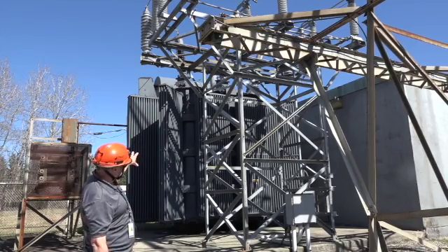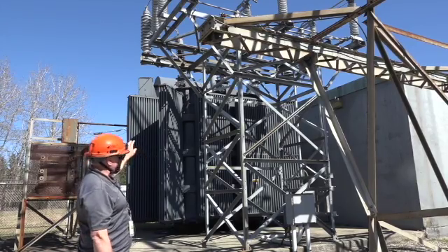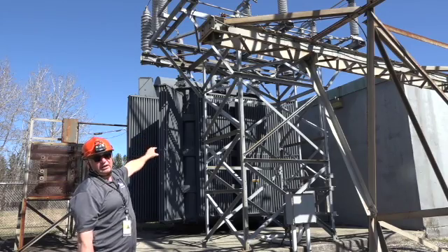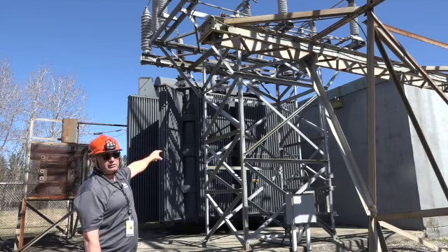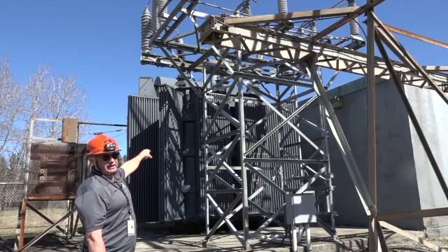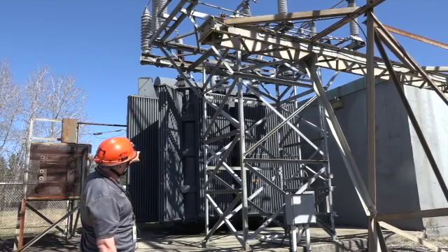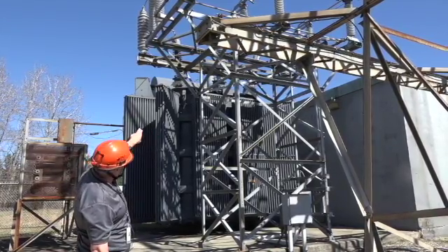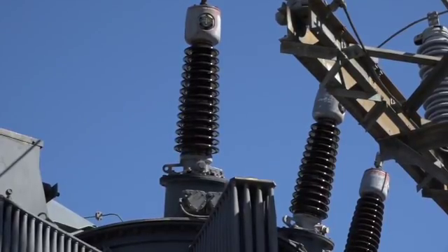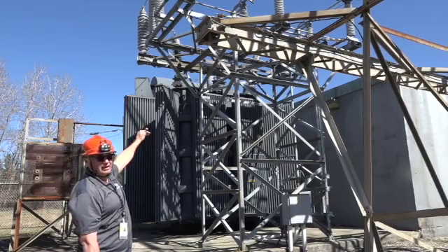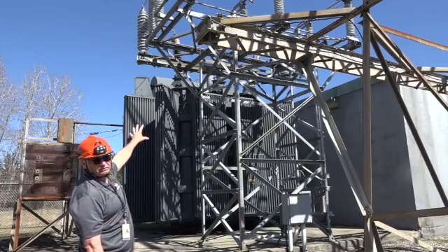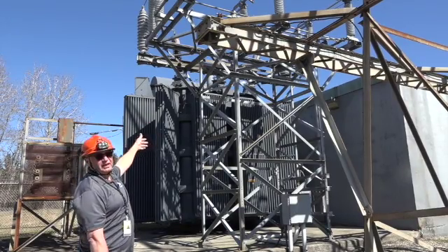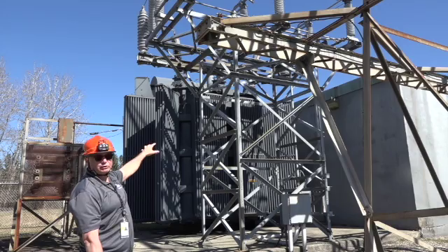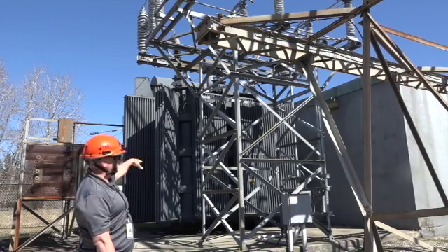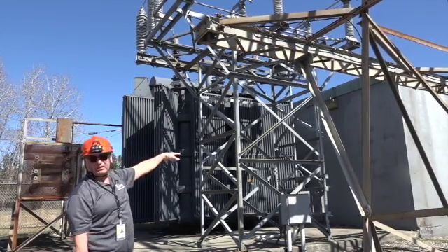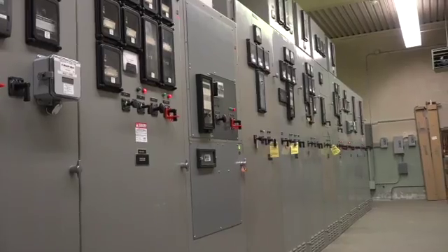In back of the switch, you can see that's a 15 MVA, 115,000 volt to 13.8 thousand volt transformer. The high side bushings that you can see up on top are about 5 foot tall. That's the 115,000 volt primary side, and then the transformer drops that voltage down to 13.8, which then goes in and feeds the breakers in the substation.